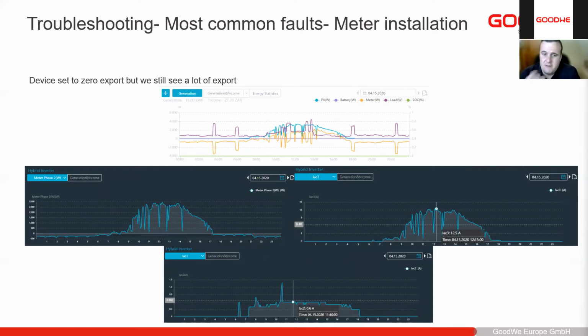So yeah, we have this device, which is a good example. It's set to zero export. Unbalanced output is enabled on this device to maximize the savings. But with this customer, we can clearly see the device still has significant export. So what happened: this customer had a phase order fault. They fixed the phase order fault, but they didn't fix it on the smart meter.